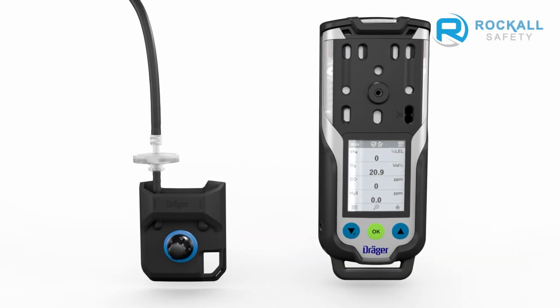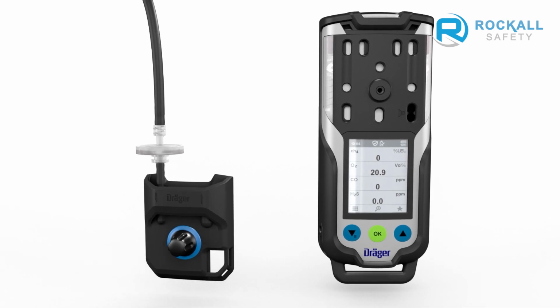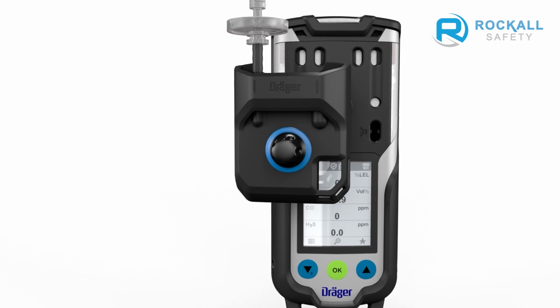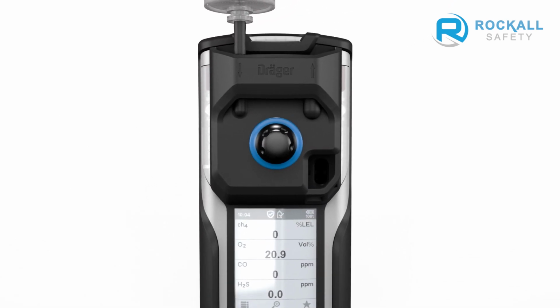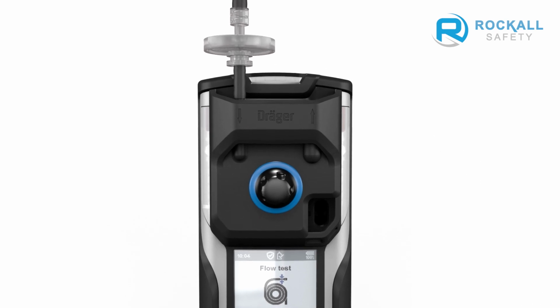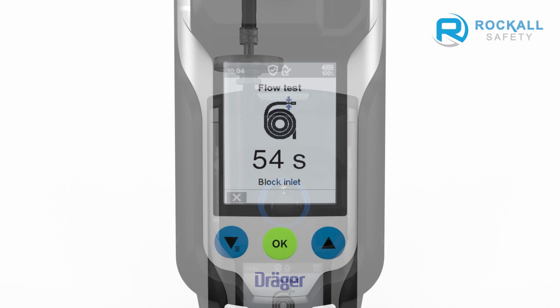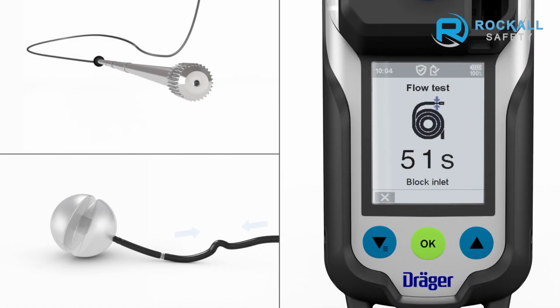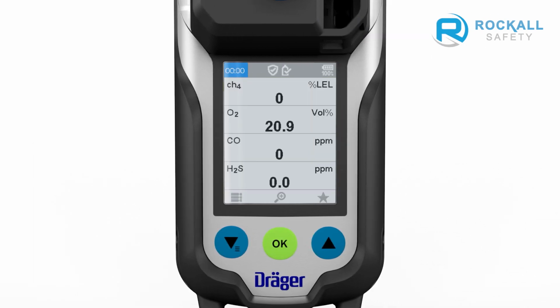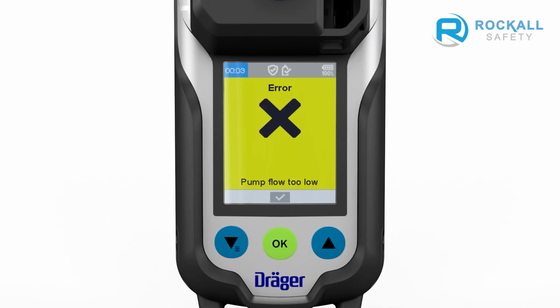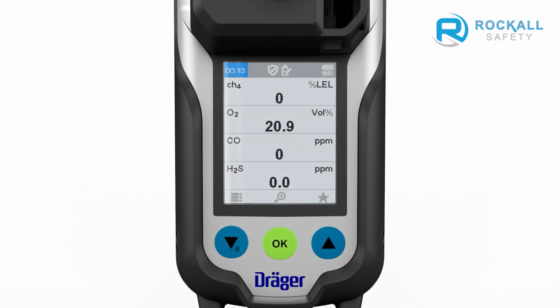The pump adapter must be screwed on in order to turn on the pump. To do this, place the pump adapter on the thread of the front cover, then align and tighten. The pump will turn on automatically. Always use the pump adapter with the dust and water filter. The pump test will start automatically. Close the gas inlet at the end of the probe until the leak test is complete. Then release the gas inlet. If the leak test is successful, pump mode will be activated. If the pump test is unsuccessful, check the probe, hose and adapter as required and repeat the test. Once the device has passed the test, it is ready for operation in pump mode.